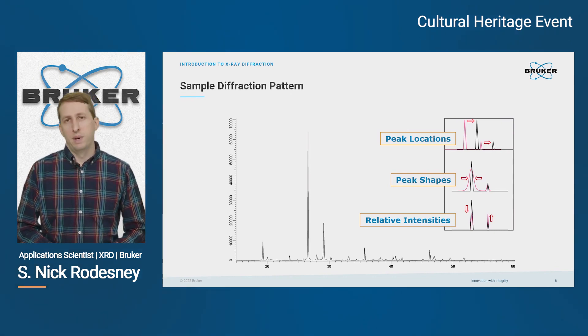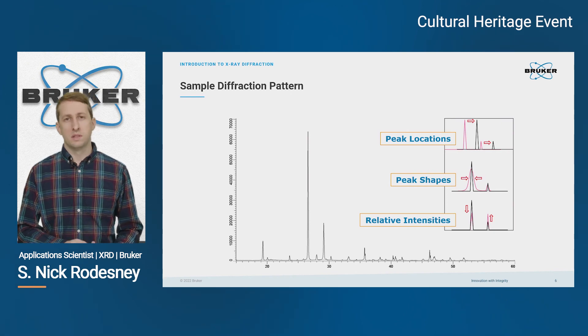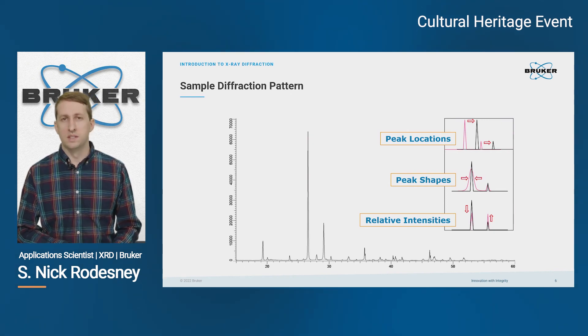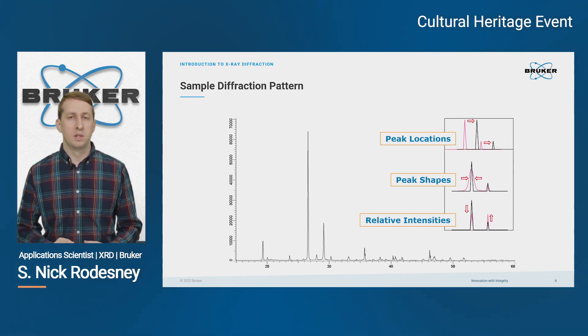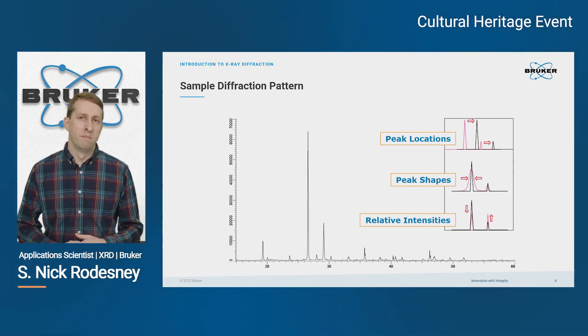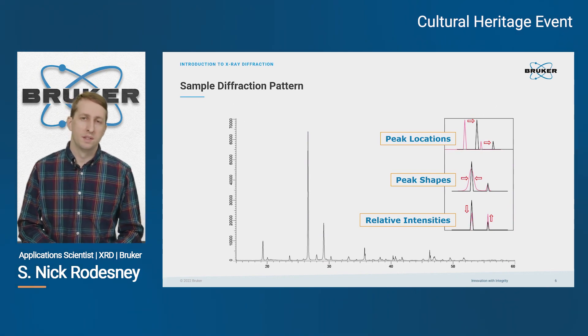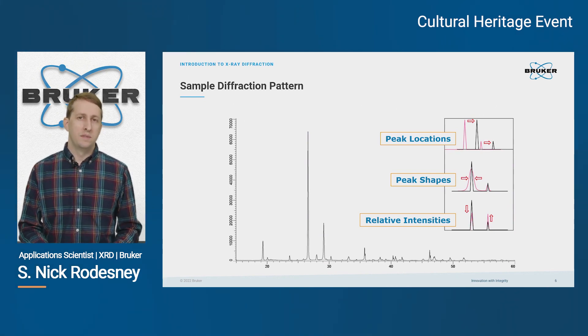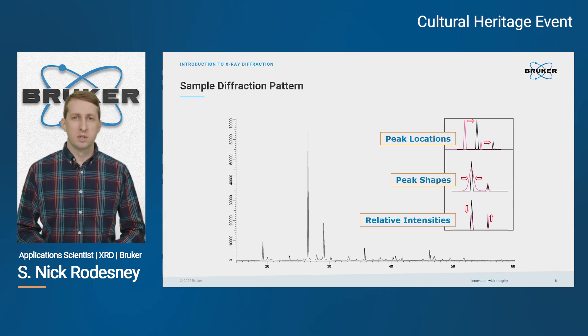When we look at a diffraction pattern like this, there are three things that we're interested in: the peak locations, the peak shapes, and the relative intensities. The peak locations will give us information about the phase composition of our material. The peak shapes will tell us about the crystallite size, and the relative intensities will help us with quantification if we have a mixture.